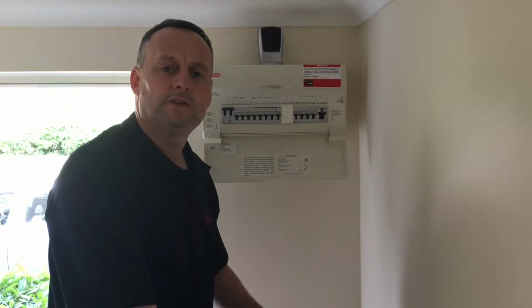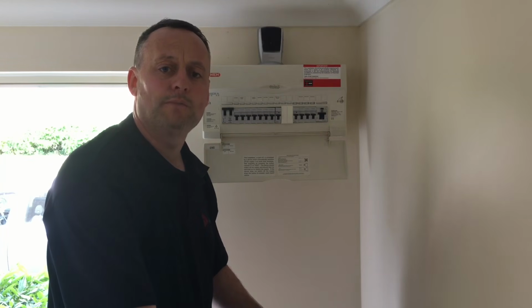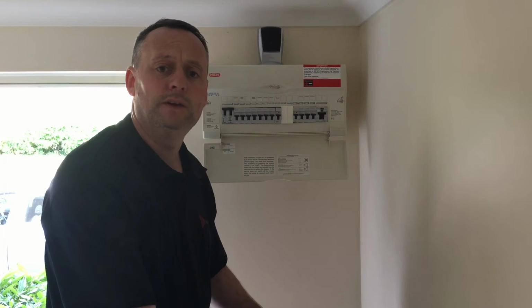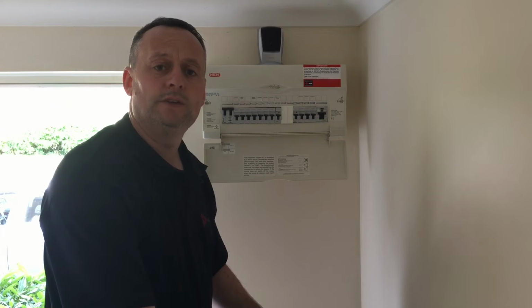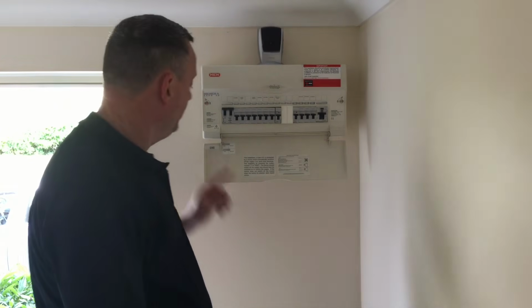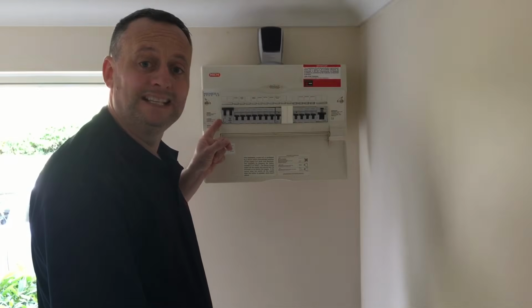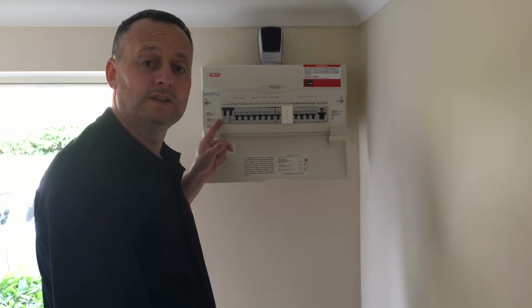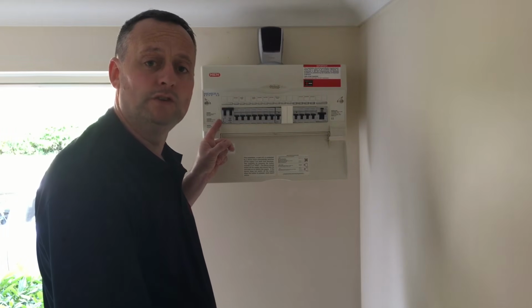In order to measure the external earth fault loop impedance in this installation, I'm going to need to take off the cover of the distribution board. I have no separate MET where I could disconnect my 16mm earthing conductor, so it must be disconnected from within the consumer unit and where it is terminated in the main earth bar. In order to do this, I'm going to need to isolate the consumer unit at the main switch, the linked main switch or double pole switch.